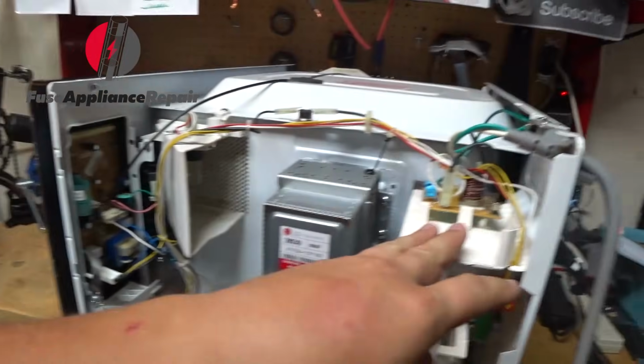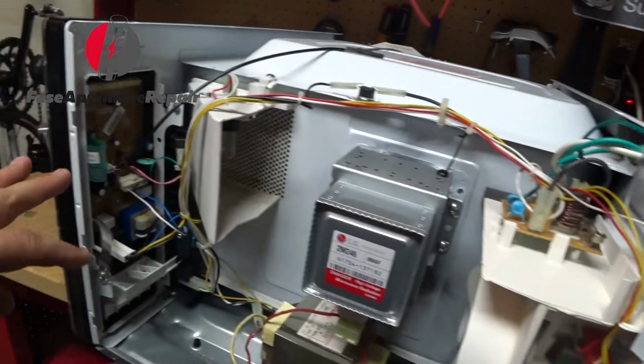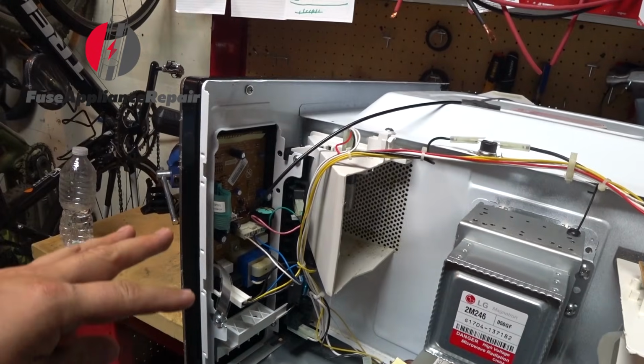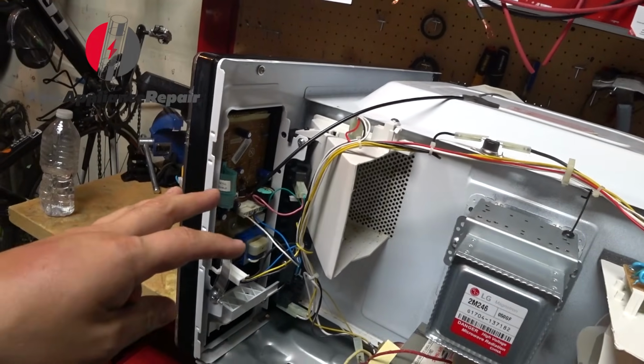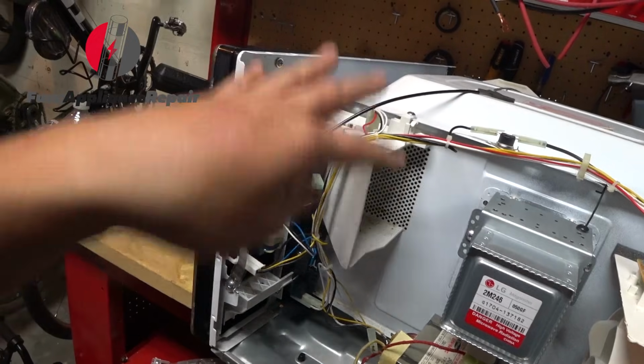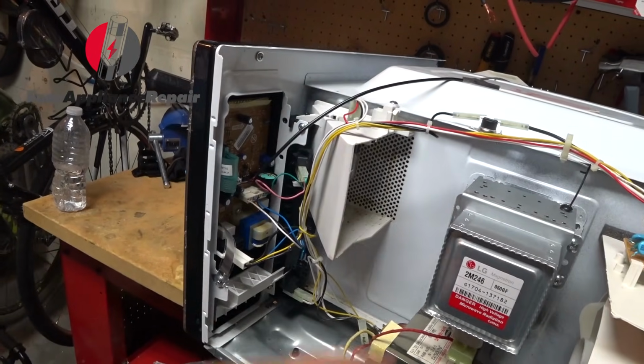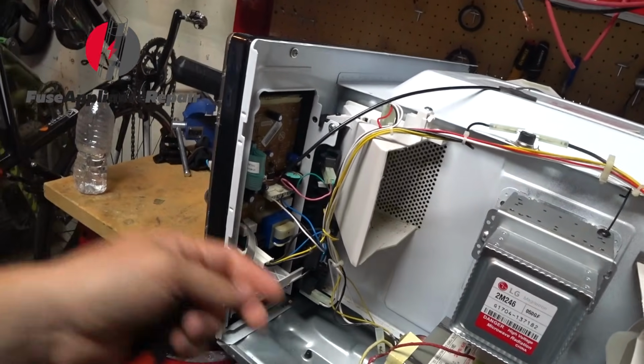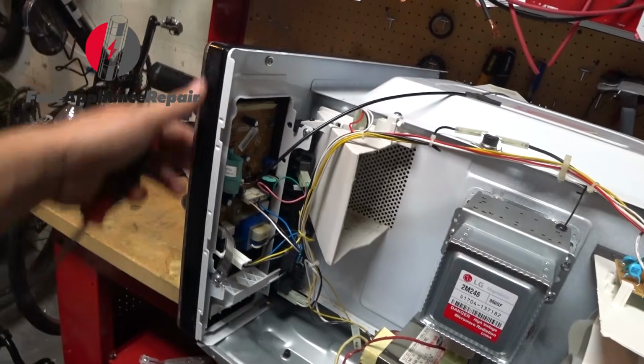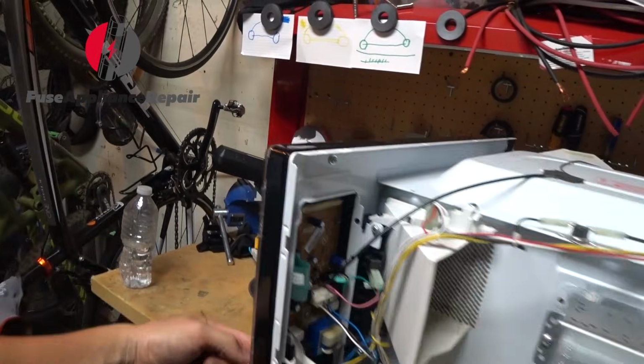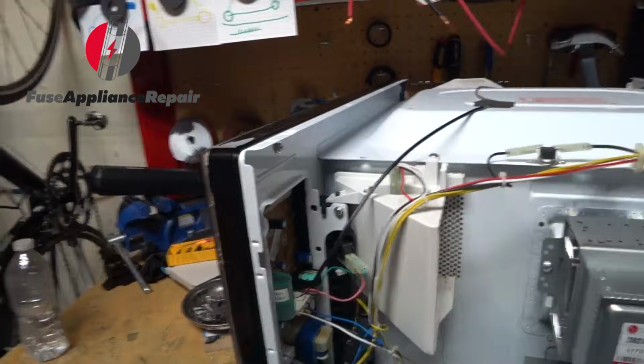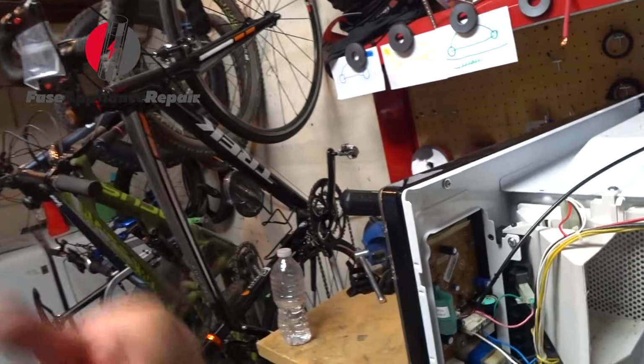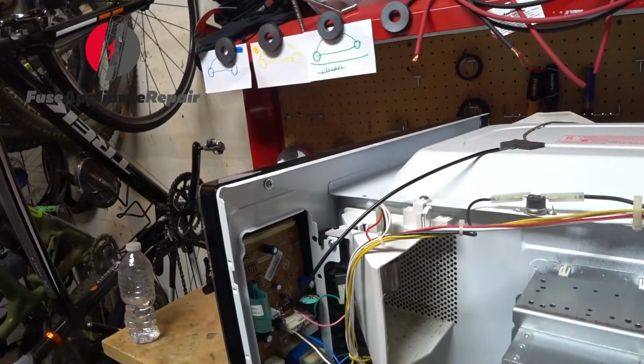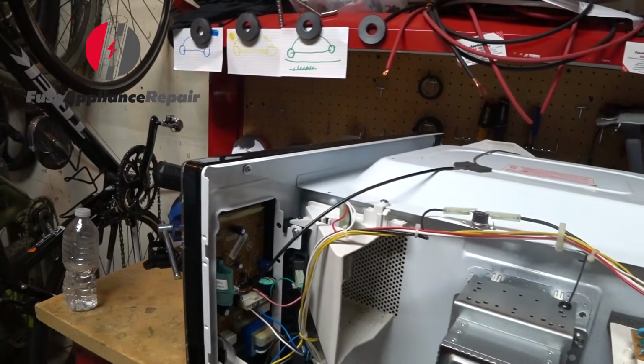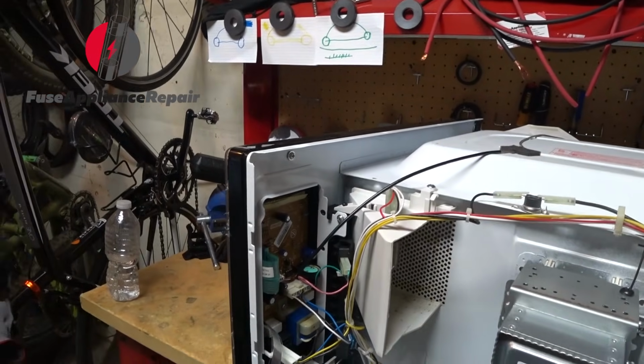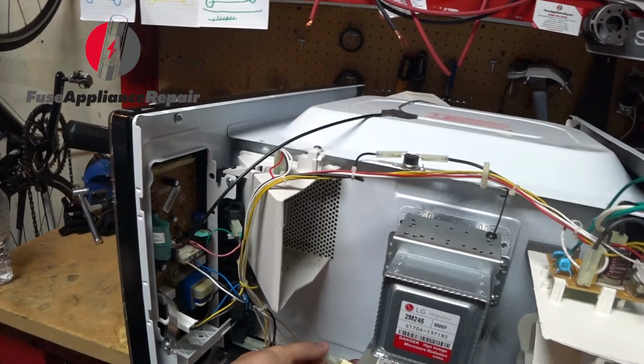If the fuse keeps blowing in this situation, that means the problem is with your low voltage, 120 volt circuit. If you run the heat program and it counts down the seconds, that means everything with the low voltage part is okay. Then you can move on to the high voltage part.